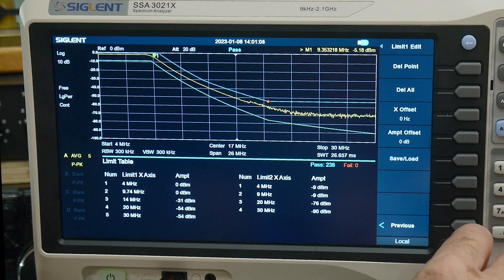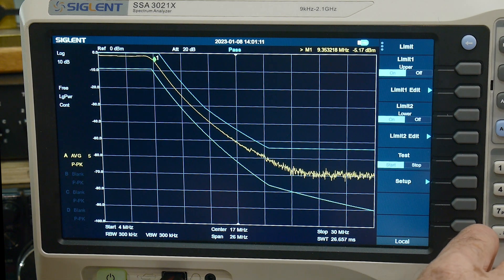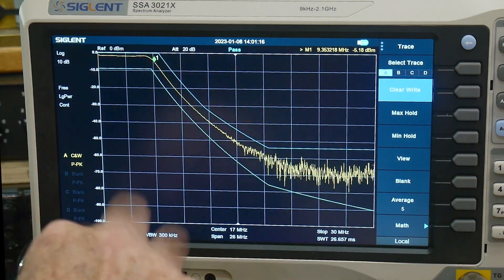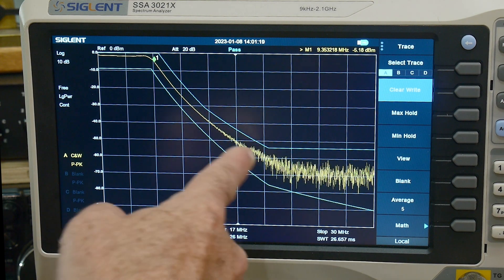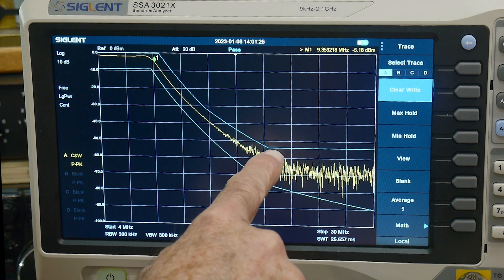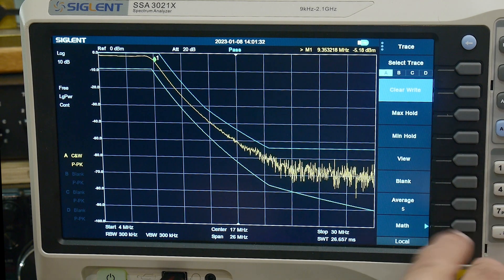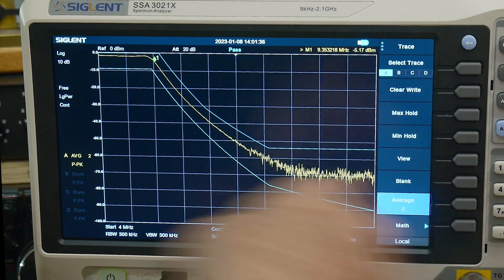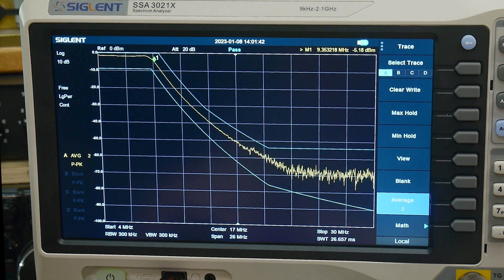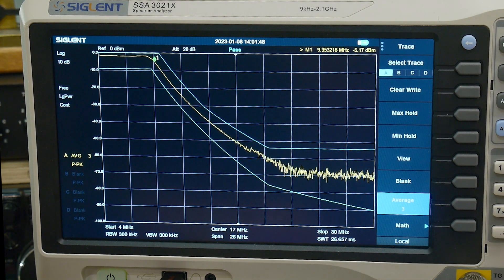One thing I've noticed is that if you have no averaging on — just one — every once in a while the noise will be just above your pass line. So you probably want a little bit of averaging on your trace. I have it set to average five; you could probably set it to average two or three, which is even faster. You want fast detection but a little averaging so you're not tripping your limits all the time.